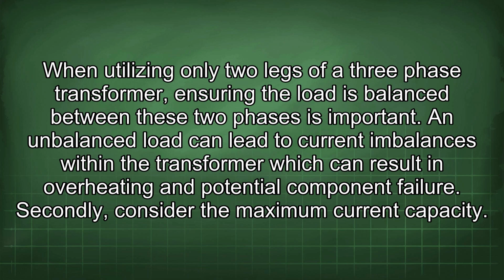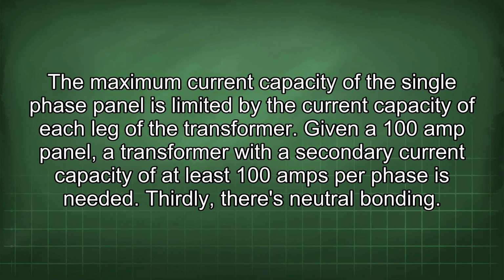Secondly, consider the maximum current capacity. The maximum current capacity of the single-phase panel is limited by the current capacity of each leg of the transformer. Given a 100 amp panel, a transformer with a secondary current capacity of at least 100 amps per phase is needed. Thirdly, there's neutral bonding.